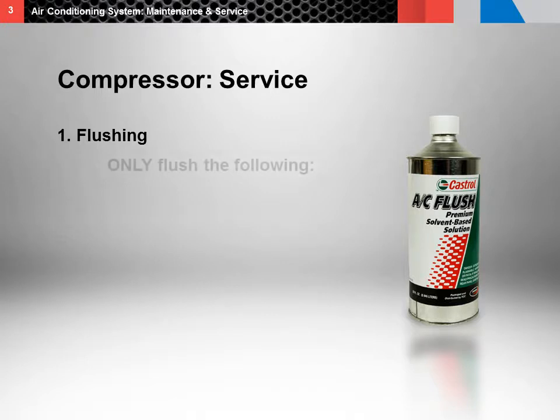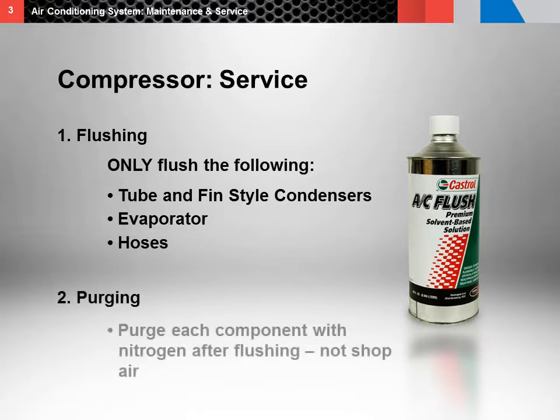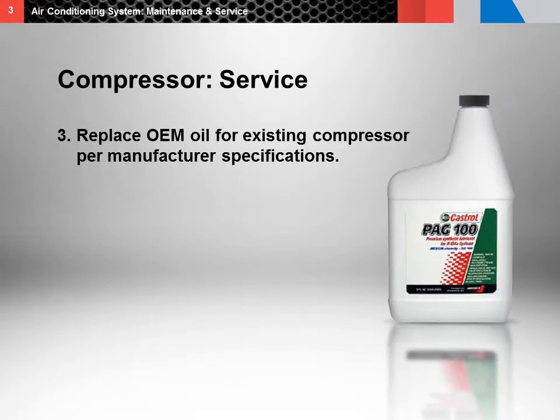Only flush the following components: tube and fin style condensers, evaporator, and hoses. Then purge each component with nitrogen after flushing, but not with shop air. During the flushing procedure, most of the refrigerant oil is removed, so add the total oil charge for the system. If we're using the existing compressor, check the oil in the compressor and subtract it from the total system oil charge.